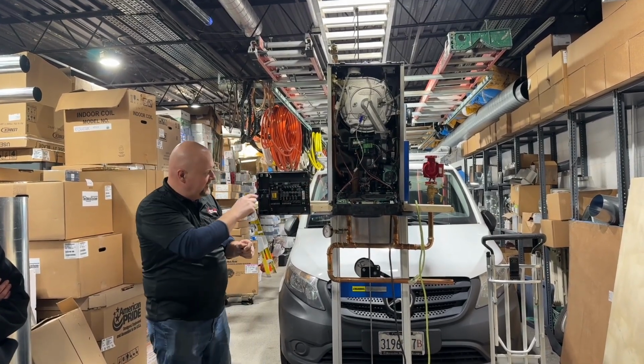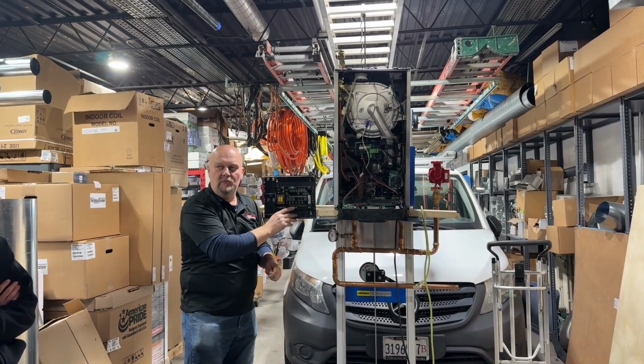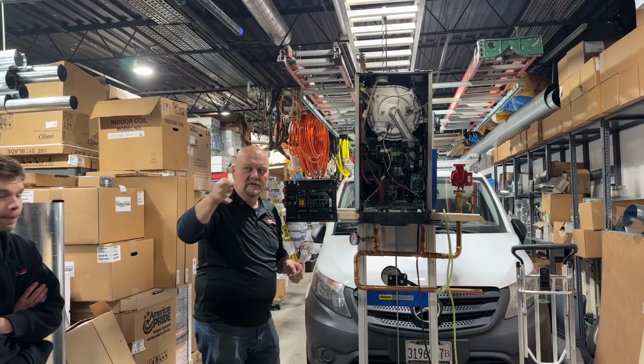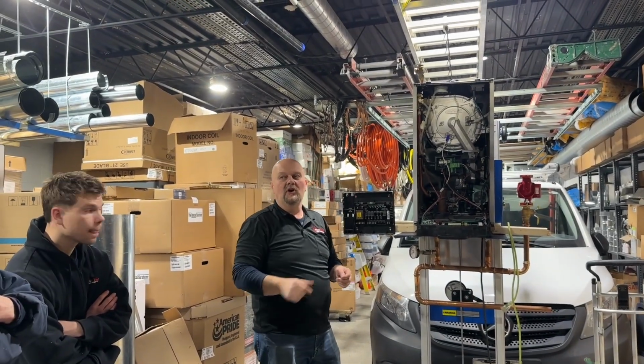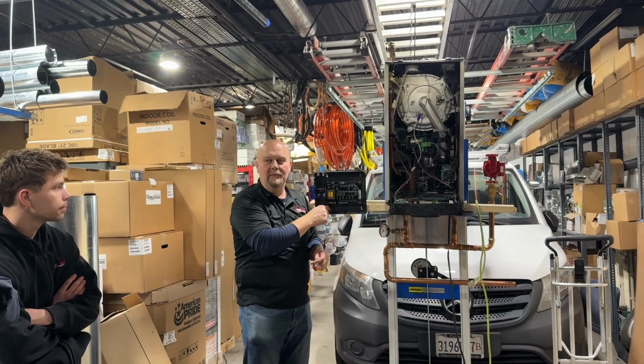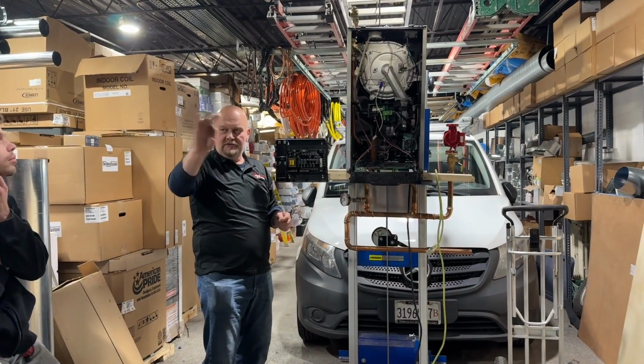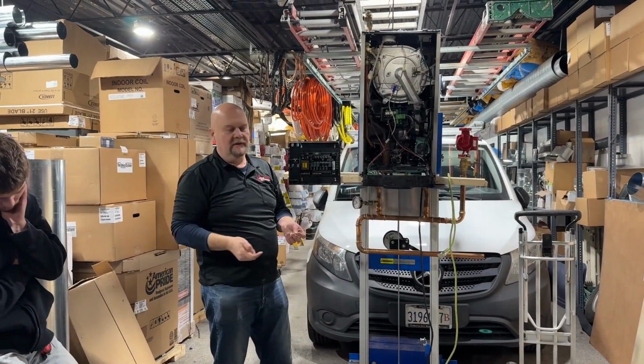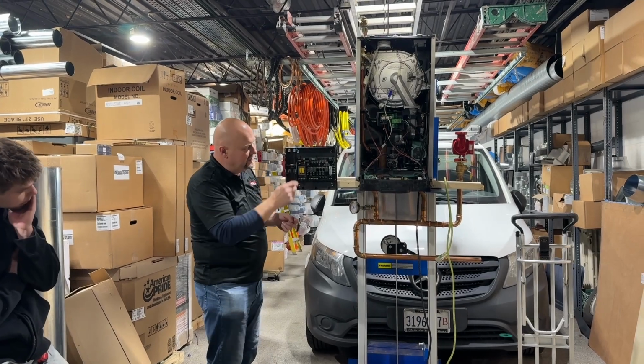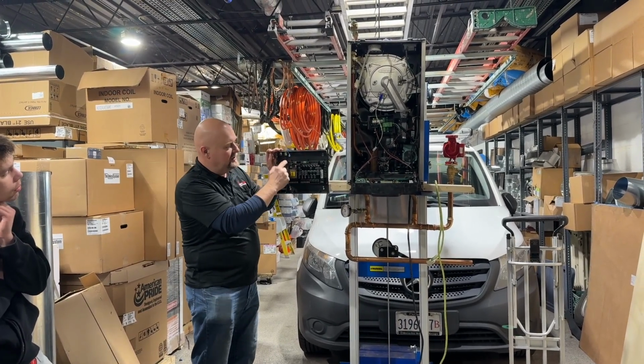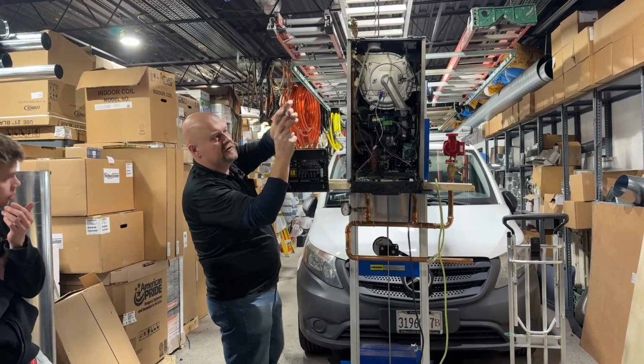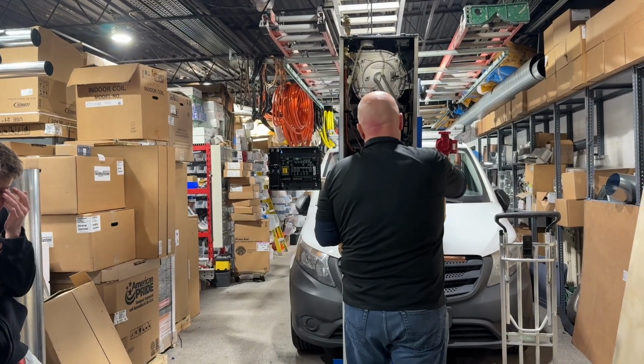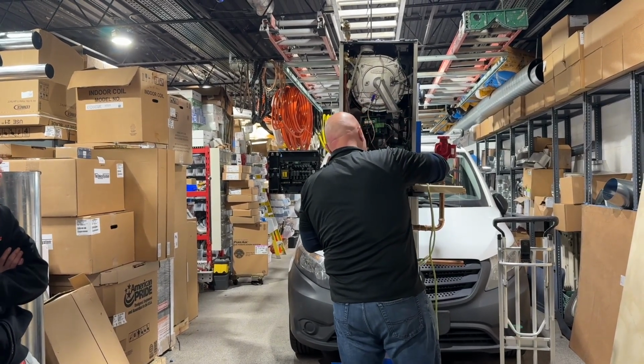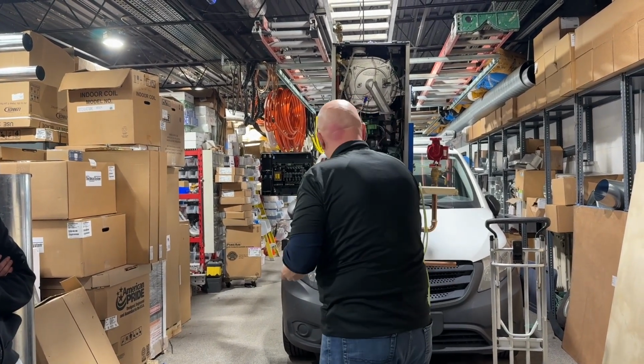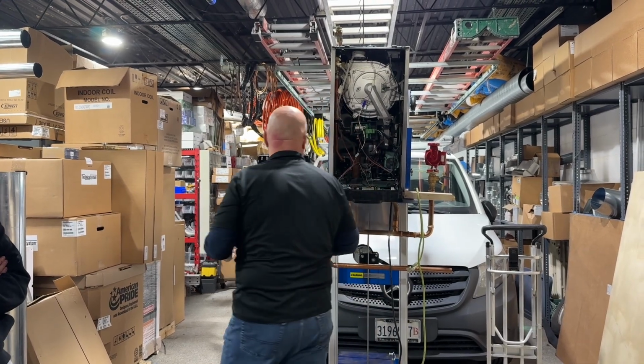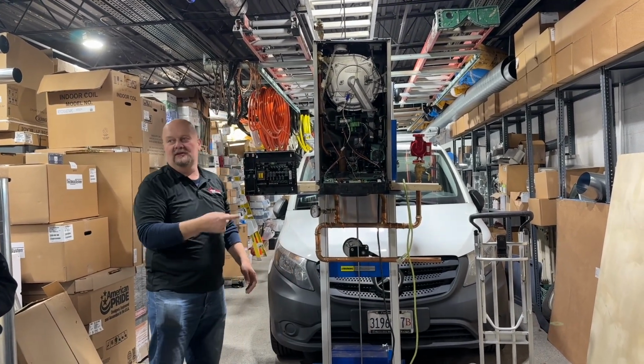So that's why you're going to see on all these control boards, like a control board for zone valves instead of pumps, this is a pump control board, right? But you can also have different zone valves. So when you have something like this, you're going to have these X and X. You're going to have a 2-wire go from X and X to this, and that's basically what fires up the boiler. Unfortunately, there's no water in the boiler, so I was going to start it up, but it just gives me a pressure code because it realizes there's no water in it.